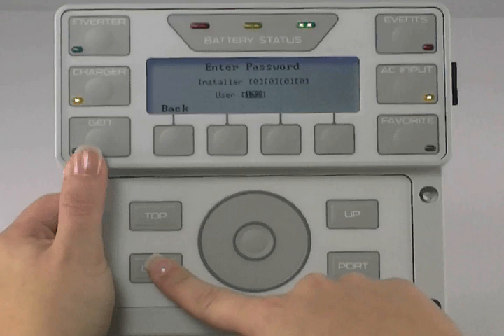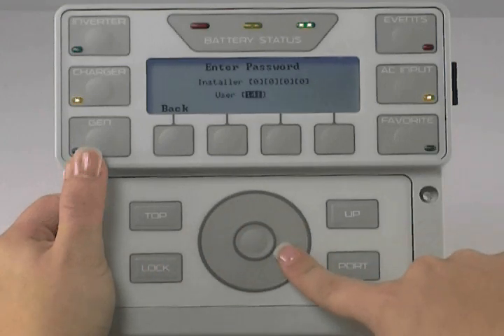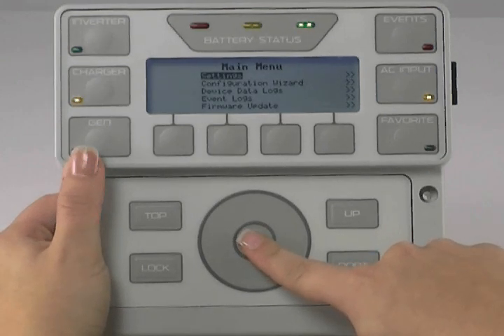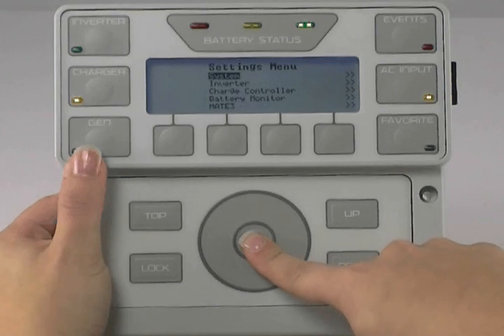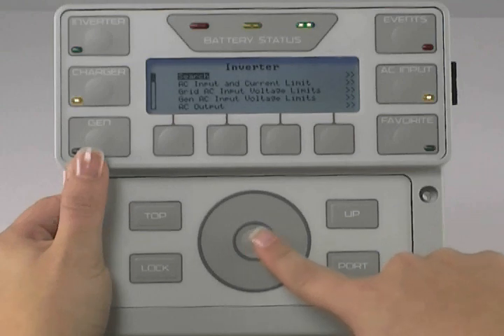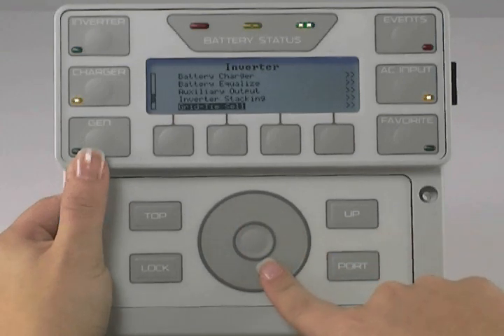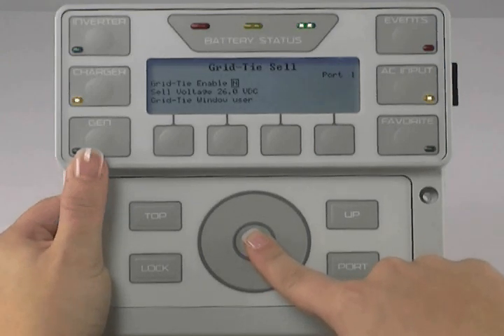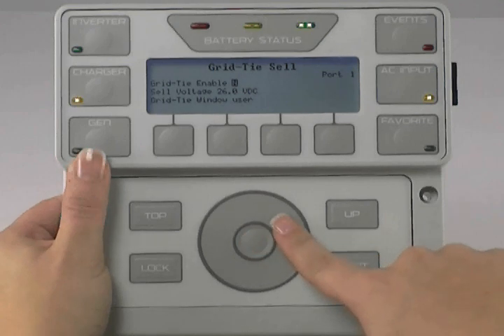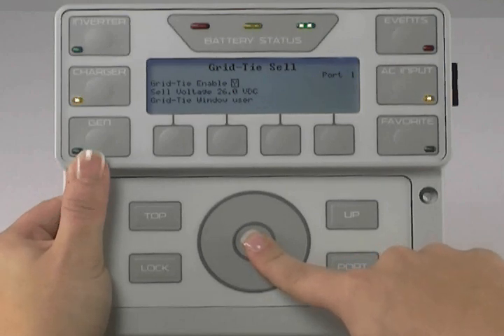On your Mate 3, press the lock button and use the wheel to change your user password to 141. Press the center button. Make sure Settings is highlighted and press the center button to select. Use the wheel to highlight Inverter and press the center button. Use the wheel to highlight Grid Tie Sell, press the center button, then press the center button again to highlight Grid Tie Enable. Use the wheel to change this to Yes, then press the center button to lock in your selection.